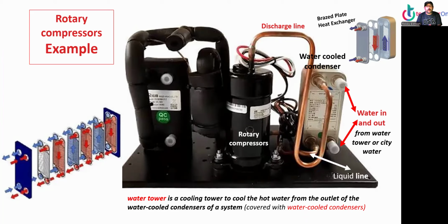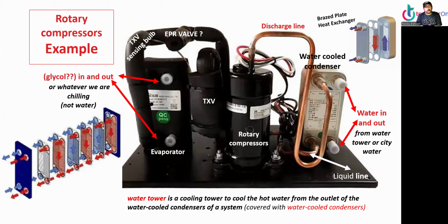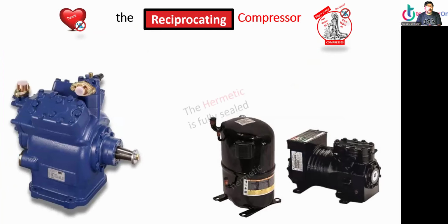All right, next. There's the liquid line out at the bottom, and then the liquid line out to the thermostatic expansion valve, the expansion valve sensing bulb. This must be an EPR or something. I cannot tell, it's covered. And then the evaporator. It could be glycol. I don't think it's water, it will freeze. Maybe glycol. And this is the plate heat exchanger used as an evaporator. Alrighty, and we'll cover that more in the evaporator and condenser section. All right, now let's move on.